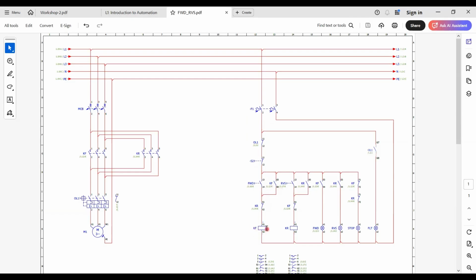Now since KF1 is energized, the motor is running in the forward direction. So similarly, there's another auxiliary contactor normally open, which connected to 53 and 54 of the same contactor. So when this coil is energized, the power contacts close as well as this auxiliary contact close, that will illuminate the forward light indicator. So the operator can see that the motor is rotating in the forward direction and the forward light is lit.